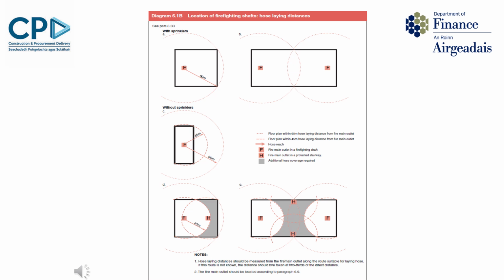Figure D illustrates a situation where provision of a firefighting shaft alone satisfies the first criteria of all parts of the floor being within 60 metres of a fire main in a firefighting shaft. However, it does not meet the additional second criteria of each part of the floor being within 45 metres of a fire main, either in a firefighting shaft or in a protected stairway. So the grey bit in the figure is not covered. The solution to make it compliant is to fit another fire main, either in a second firefighting shaft or in a protected stairway. So this figure illustrates provision of a fire main outlet in a protected stairway. Provision of a fire main in a protected stairway would be a cheaper option than provision of a second firefighting shaft.